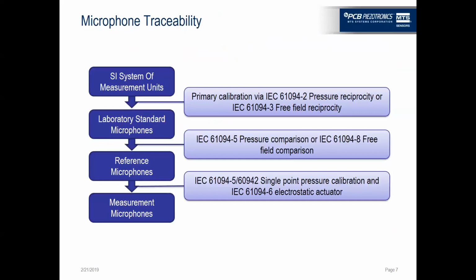And again, this is just fundamentally going through, but then applying the standards to it. So first, we start with the base units of the metric system, and in order to get from those base units into a microphone calibration, we do a primary calibration by pressure or free field reciprocity. That creates an artifact called a laboratory standard microphone. And from there, the laboratory standard microphone can be used either via primary calibration or also a pressure comparison or a free field comparison calibration in order to create a reference microphone.